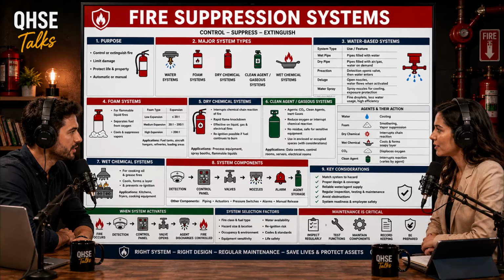Exactly. Routine visual inspections are designed specifically to catch loading. And if a head is loaded, you don't try to clean it and risk breaking the bulb. You replace the head entirely. That makes perfect sense.